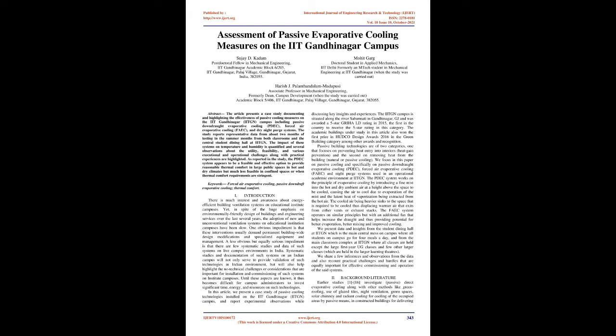As reported in the study, the PDEC system appears to be a feasible and effective option to provide reasonable thermal comfort in large public spaces in hot and dry climates, but much less feasible in confined spaces or when thermal comfort requirements are stringent. Keywords: forced air evaporative cooling, passive downdraft evaporative cooling, thermal comfort.